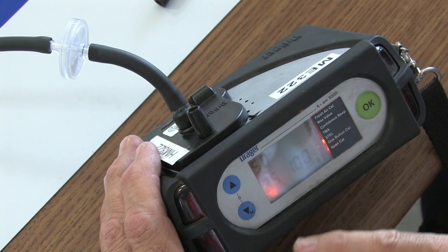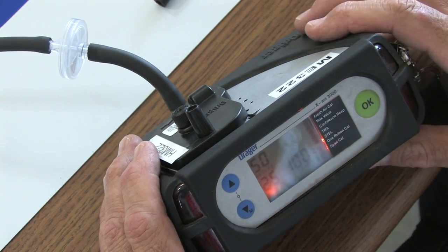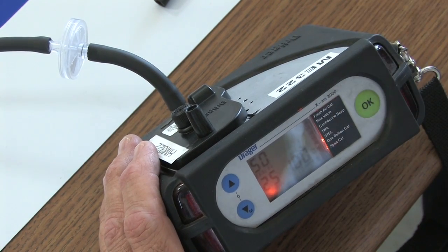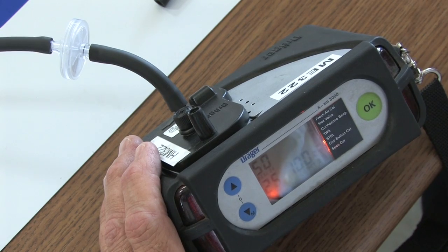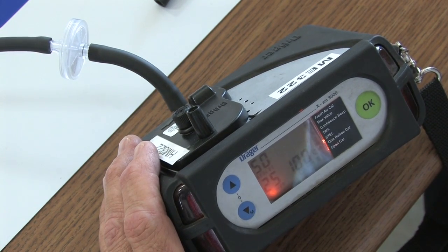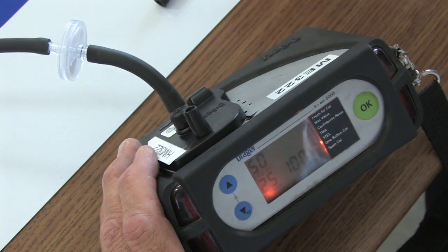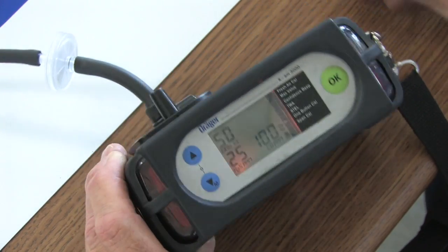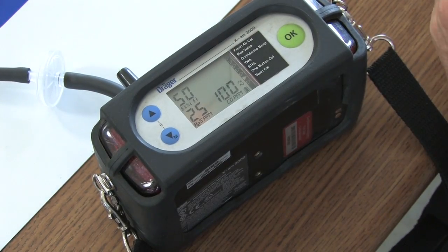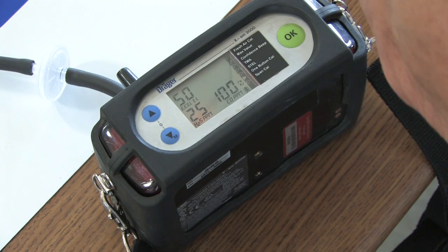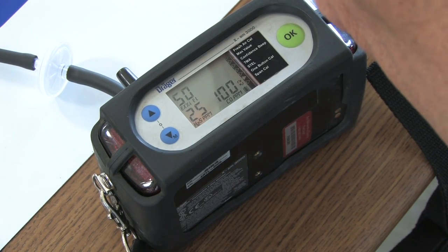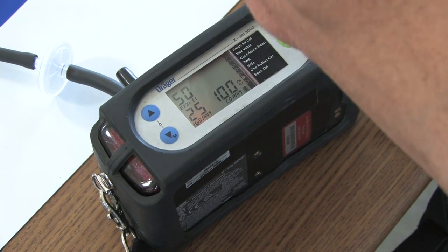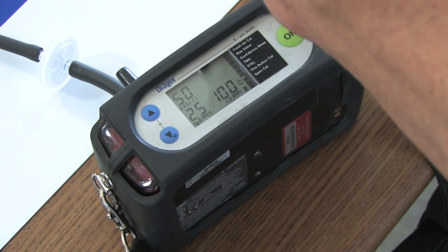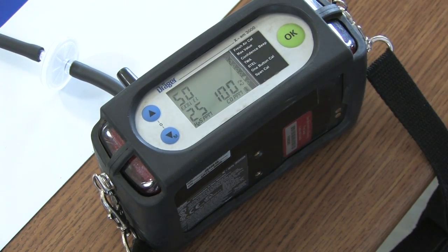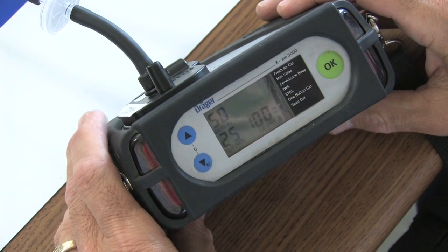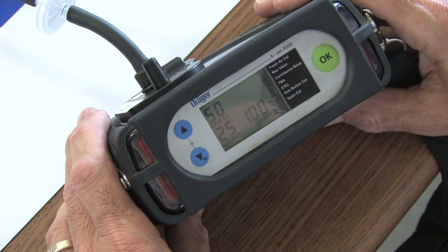Now, here are the numbers that the instrument is expecting. Notice that the oxygen is removed because when you do a fresh air cal, that's your calibration for oxygen. You do not have to blanket this with nitrogen to drive it to 0. So I'm going to hook up my gas. You don't touch anything. All you do is you hook the gas up while the numbers are sitting there staring at you. Just hook up the gas, and when the instrument starts to detect the gas, it will start making its movements. And here we go.